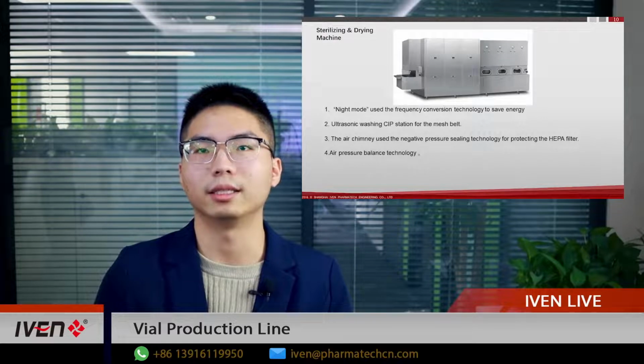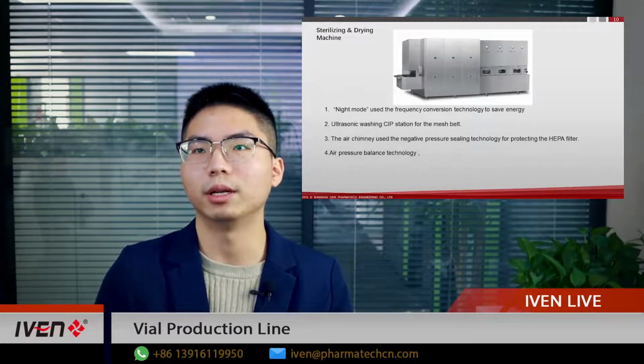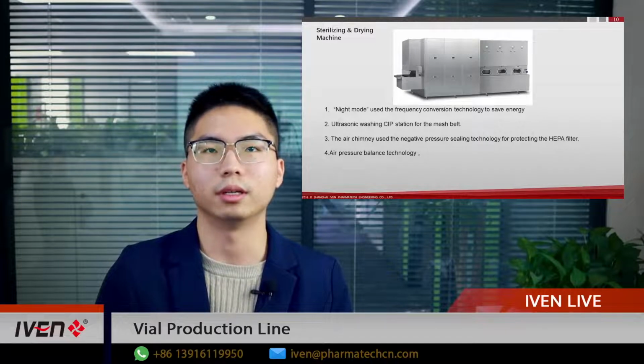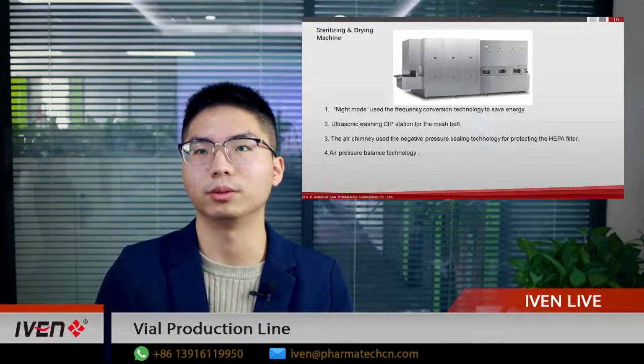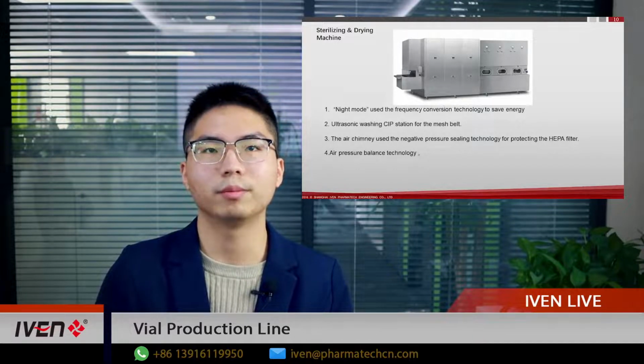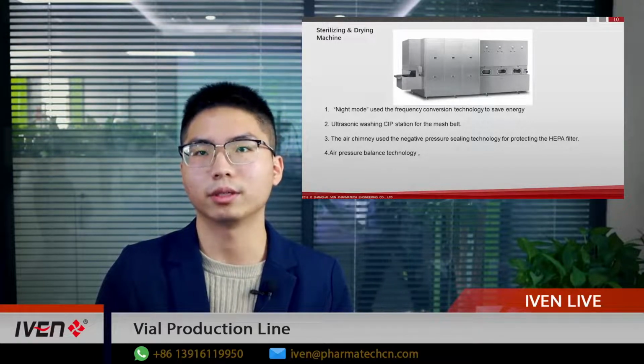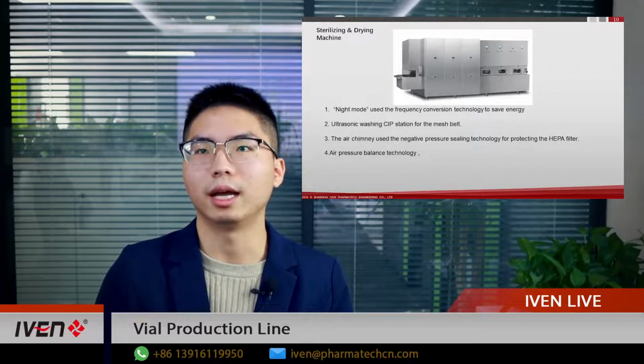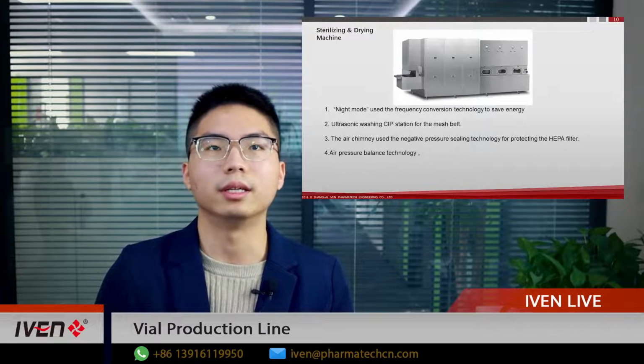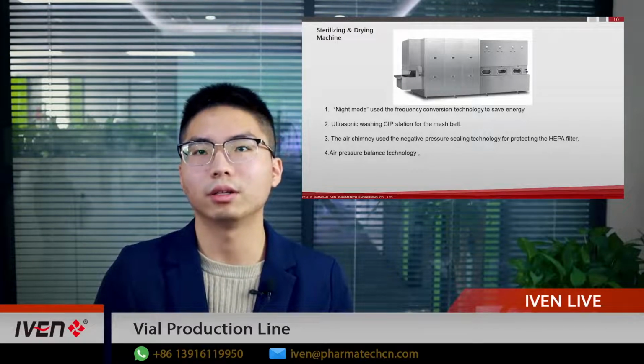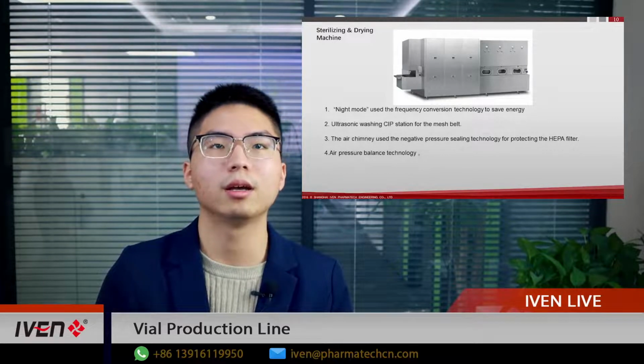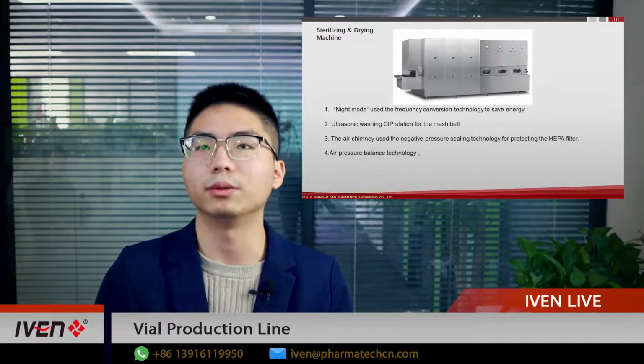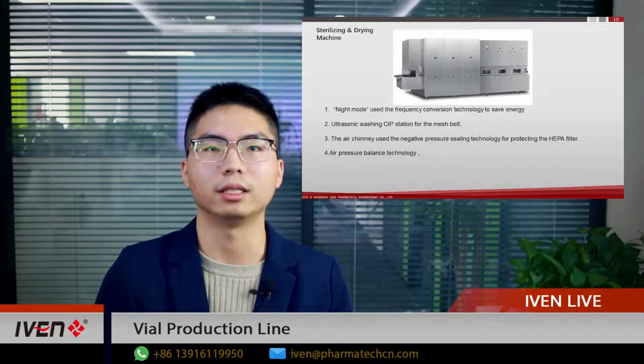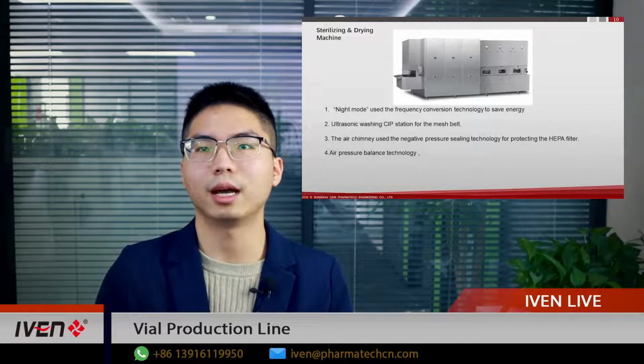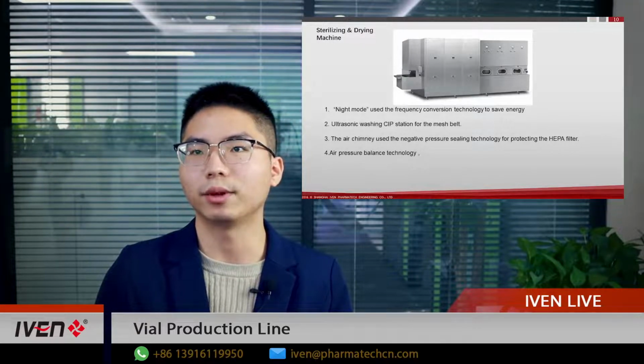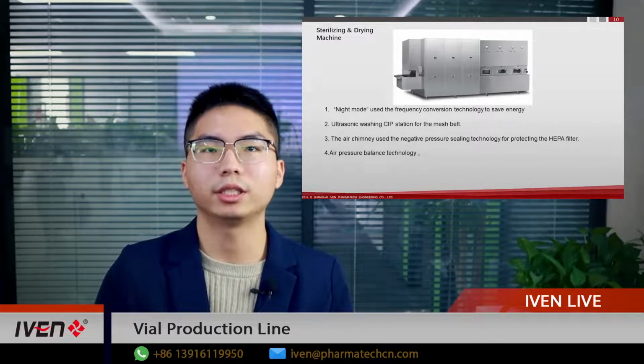Next, let's come to the sterilizer. There are also some features below. It has a night mode, using frequency conversion technology to save energy, and a mesh belt cleaning function. It is also equipped with an ultrasonic CIP station. And the air chimney uses negative pressure sealing technology for protecting the HEPA filter. We use air pressure balance technology to guarantee the pressure balance inside of the sterilizer. It can ensure dynamic balance against the different pressures of the operation areas.